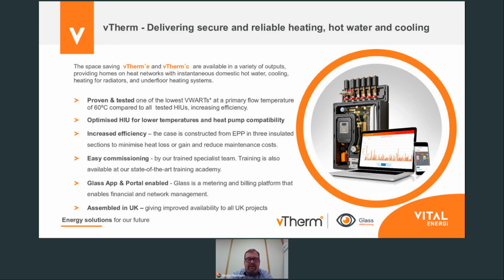So what we're trying to say is that, yes, low temperature systems are here to stay. And what we need to do is make sure that the HIUs connected to those low temperature networks are optimized and as efficient as they can be. It's all very well designing your HIU to be fully optimized for those temperatures, but we also need the ability to have control mechanisms in place to make sure systems are commissioned properly and that ongoing lifetime operation is also as efficient and optimized as possible.